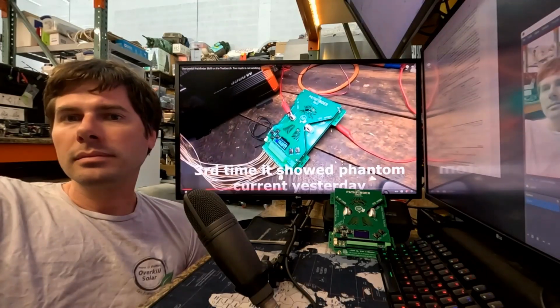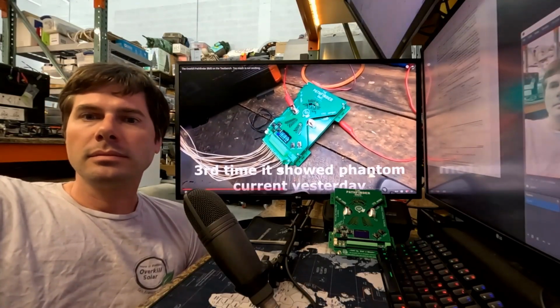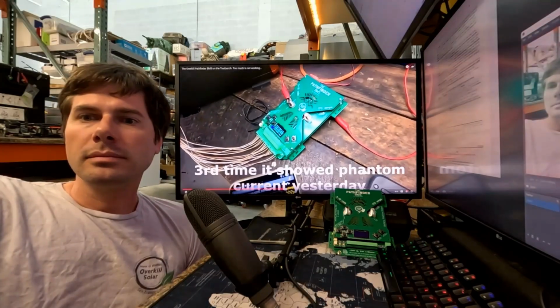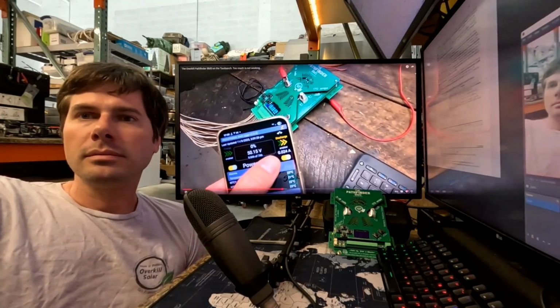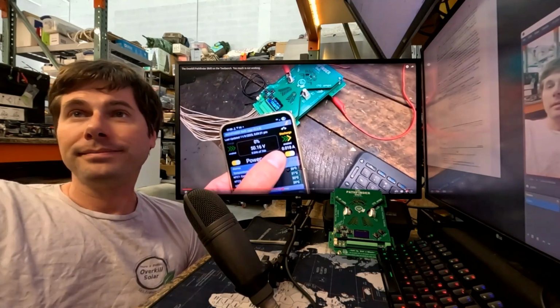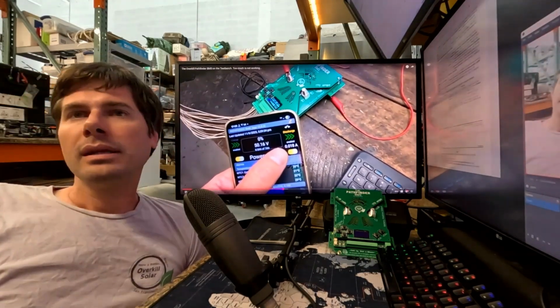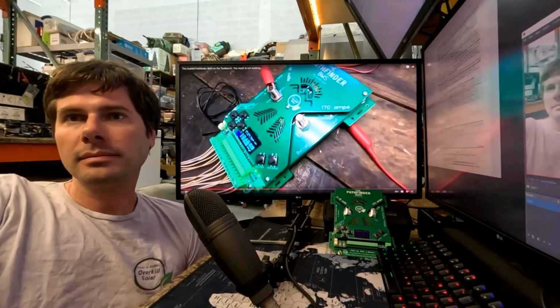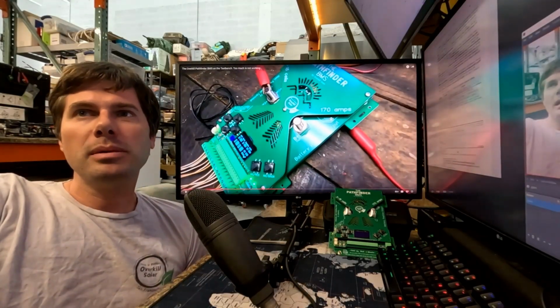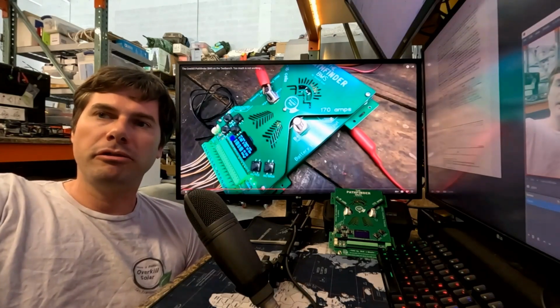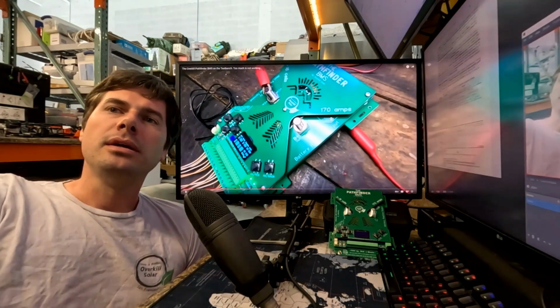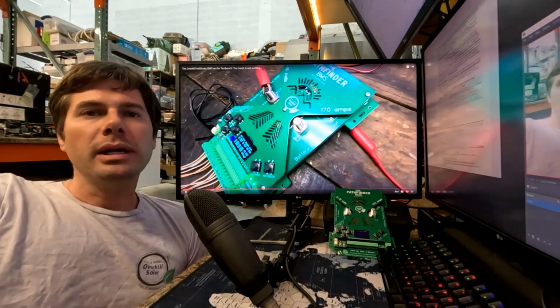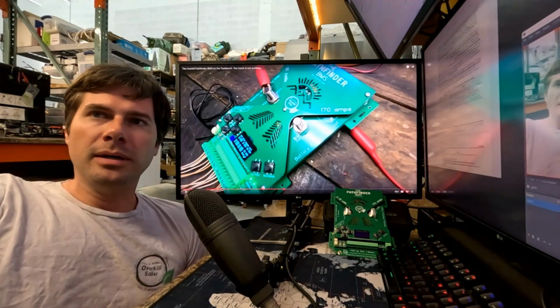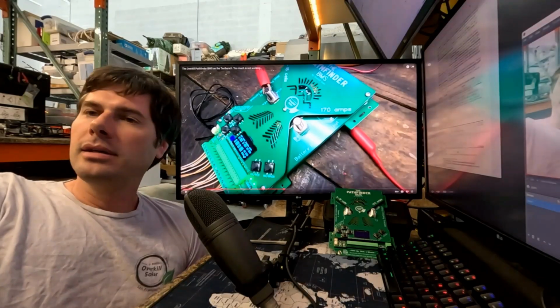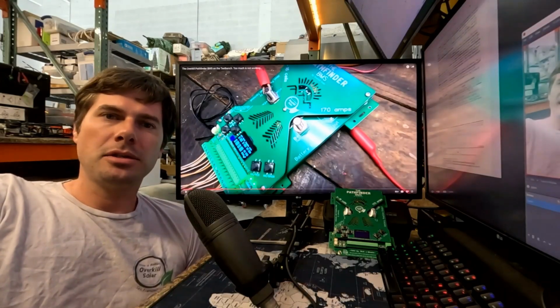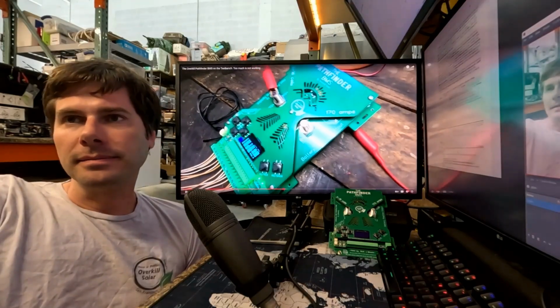This BMS had been sitting here balancing for about an hour, and we can again see we're having 24, 18, 24 milliamps of discharge current, even though there's nothing connected. I should probably just increase the deadband to about 50 milliamps on the current sensor. Maybe I'm trying too hard to get precision at low current - there's an adjustable deadband I think I've set to 12 milliamps.